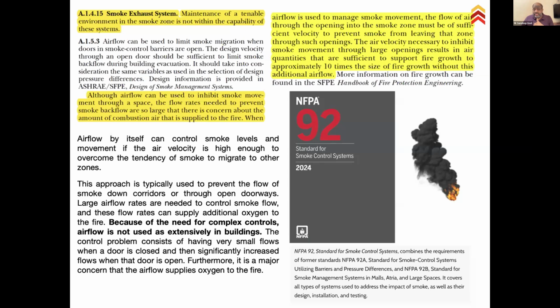The puzzle then is, why do we do a smoke management system? Why do we need to provide one? Look at NFPA 92. It was earlier NFPA 92A and 92B. Look at the italics at the bottom. It says NFPA 92, standard for smoke control systems, combines the requirements of NFPA 92A, standard for smoke control systems using barriers and pressure differentials, which was the 92A title. The 92B title was standard for smoke management systems in malls, atria, and large spaces. So it covers all types of systems used to address the impact of smoke: design, installation, and testing.